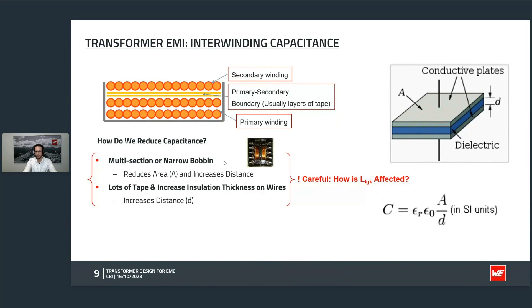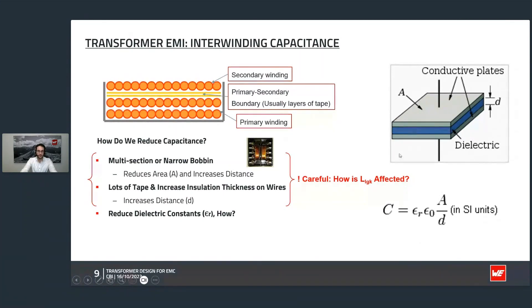We have one additional tool: the dielectric constant — epsilon zero and epsilon r. The dielectric constant will not affect the leakage inductance since it is not a magnetic property, it is a dielectric property. The material between primary and secondary has a certain dielectric constant — if we reduce it we can also reduce the capacitance without affecting the leakage inductance. So we can use varnishes or potting compounds with low dielectric properties, or sometimes it is best to use nothing at all because air already has a dielectric constant of one.